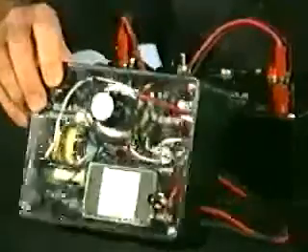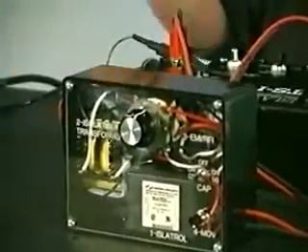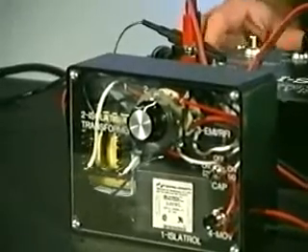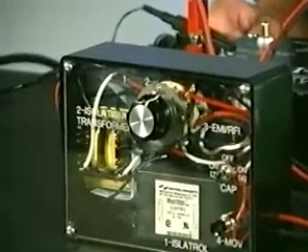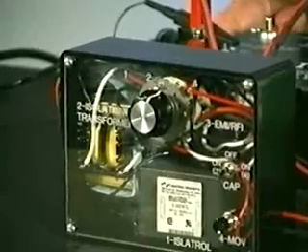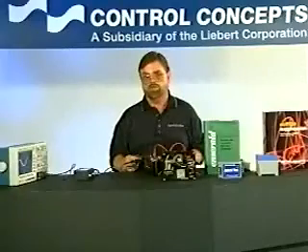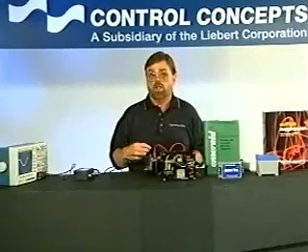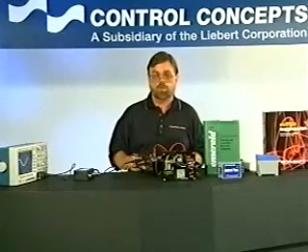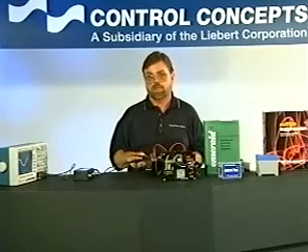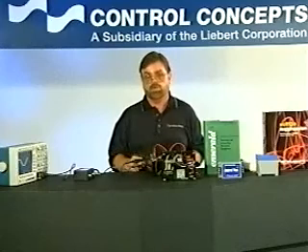The next position on the test box is an EMI or RFI filter, and basically these filters are meant to reduce any noise that a piece of equipment itself would generate back onto the power line. Unfortunately, a lot of people believe that because it's bidirectional, it would also reduce spikes or transient activity coming into the equipment.